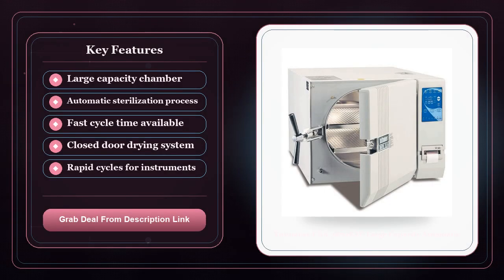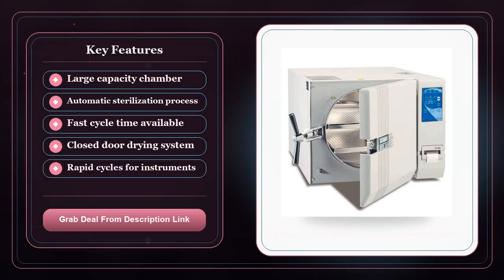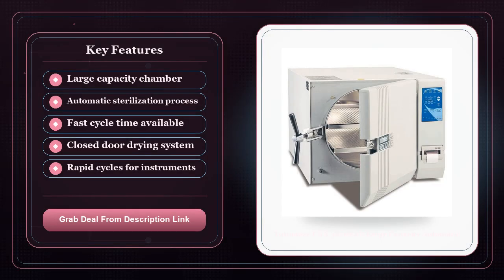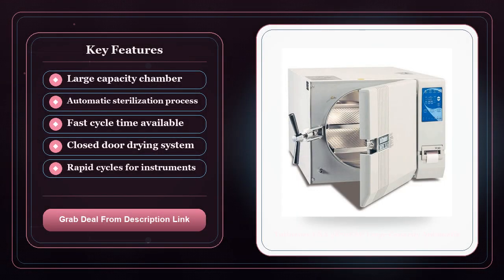Speaking of cycles, the unwrapped run time sits between 23 and 32 minutes. For most instruments that aren't wrapped in paper or foil, that's a decent sweet spot. You get a sterile batch in under half an hour, which fits nicely between appointments. If you need to run wrapped loads, say, pre-packaged sets for surgery, the time creeps up, but that's expected for any autoclave with a closed-door drying system. The active drying component is worth noting because it actively pulls moisture out while the door stays shut, keeping the chamber sterile even after the cycle ends. In practice, that means you won't have to wipe down the interior before the next load, and you reduce the risk of recontamination.